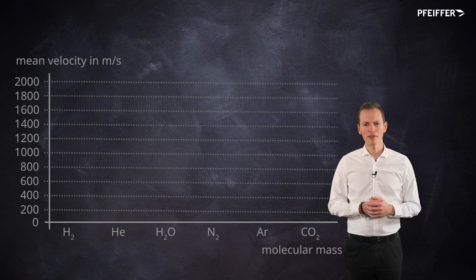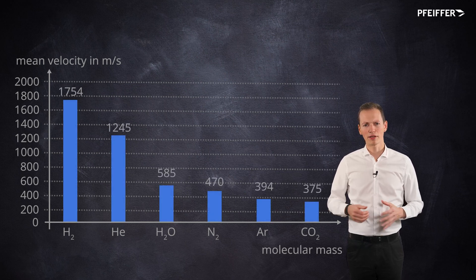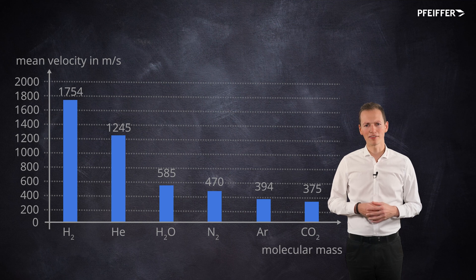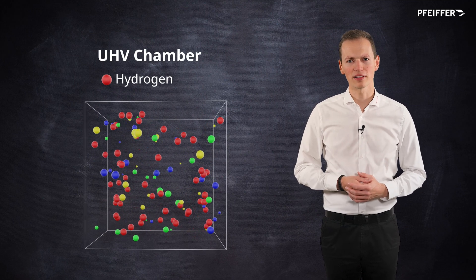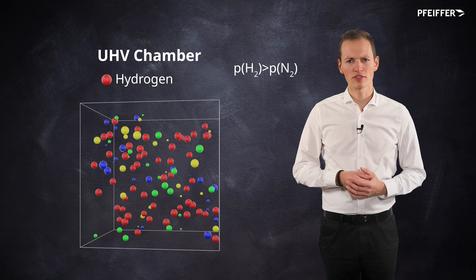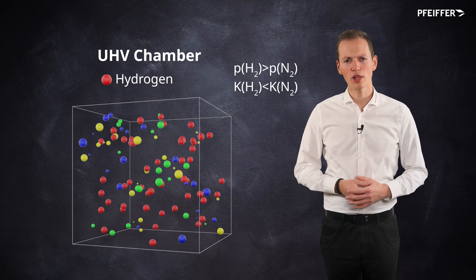The lighter the gas, the faster its molecular motion. In light gas molecules, the backflow velocity towards the high vacuum side is therefore higher than for heavier molecules. With light gas molecules, there are thus more gas particles present on the high vacuum side as a result. Therefore, the pressure is correspondingly higher and the compression ratio lower.